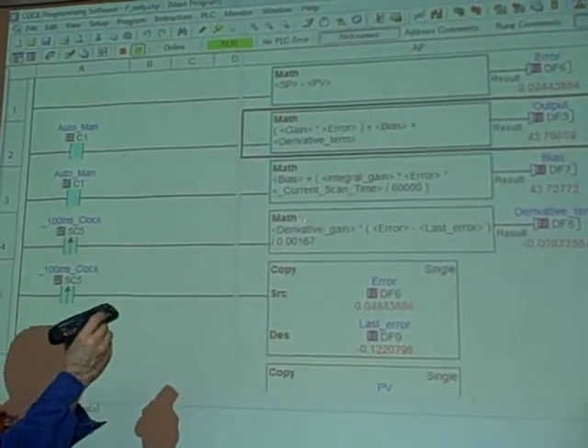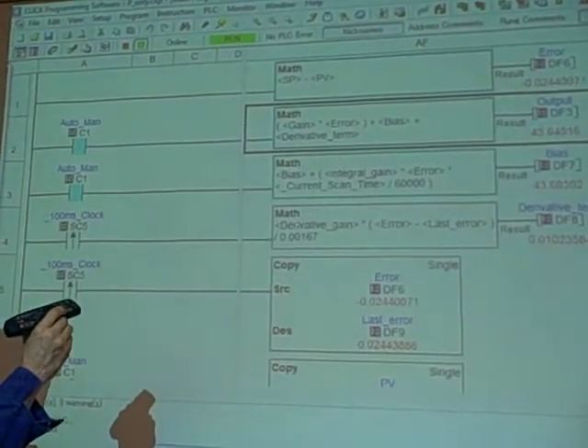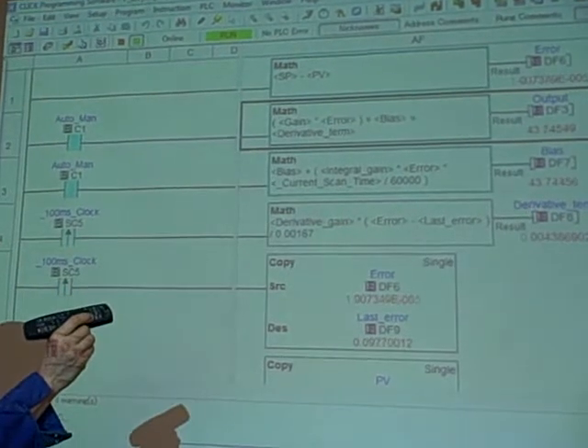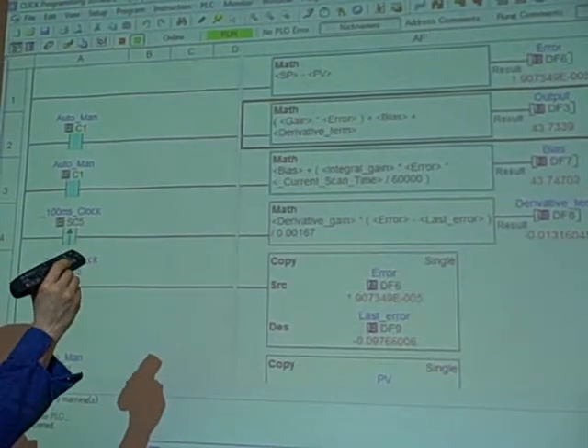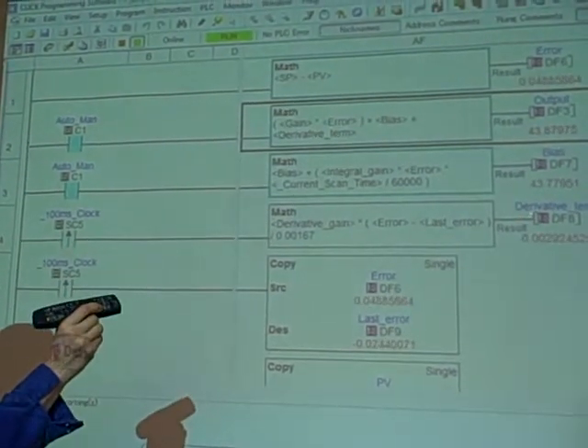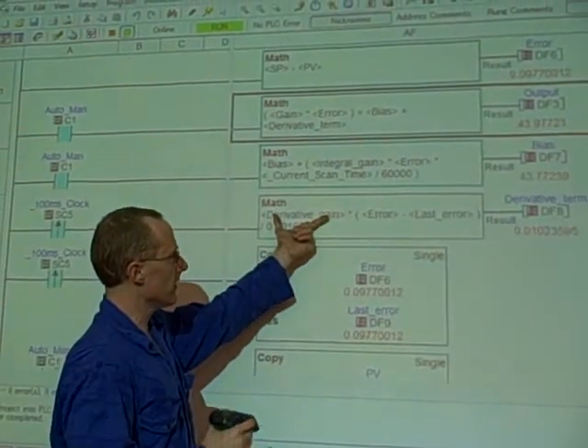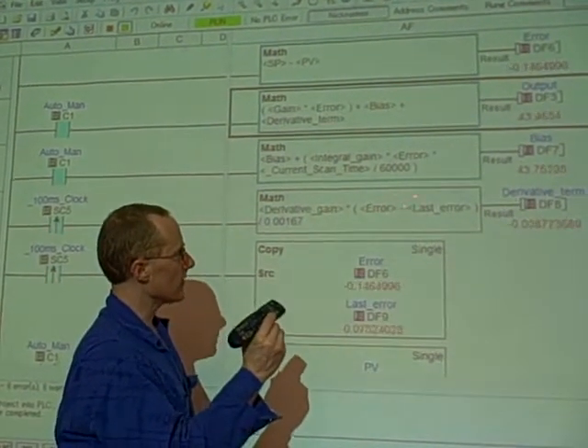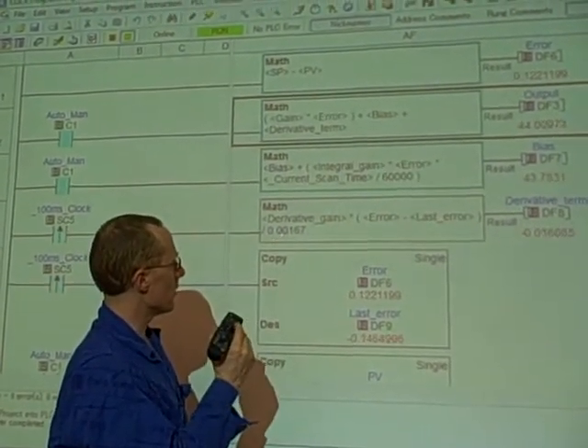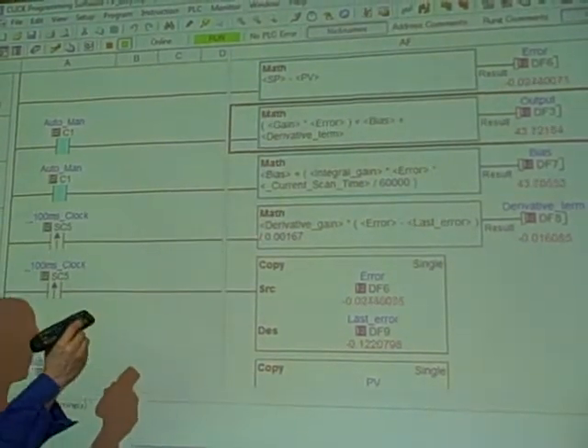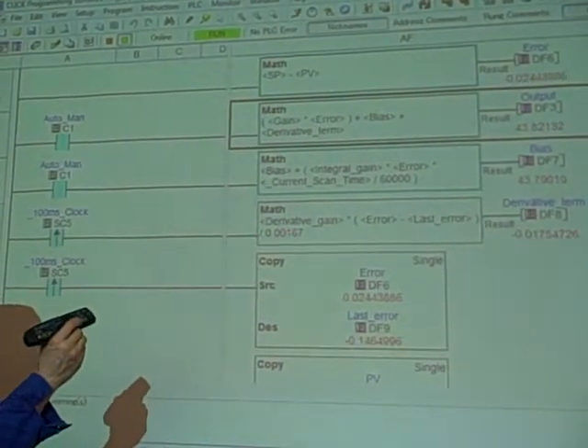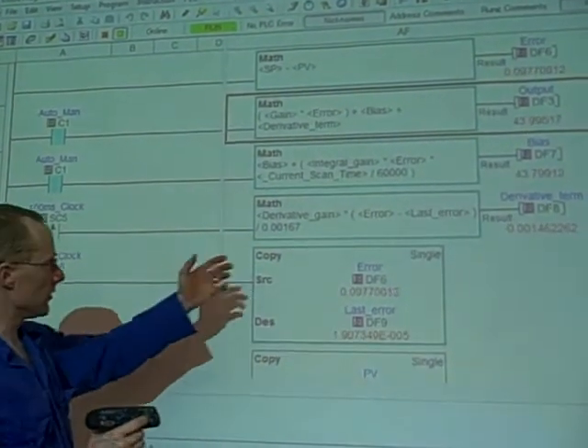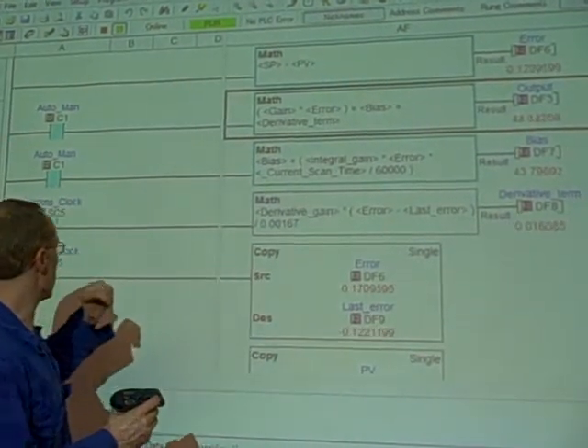Here's where we do derivative. In this case, what we're calculating is the derivative term that's going to go into that PID equation. The derivative term is based on how much derivative gain we have, times the error minus the last error, divided by 0.00167. And that's another one of those time constant parameters to put this into units of minutes.